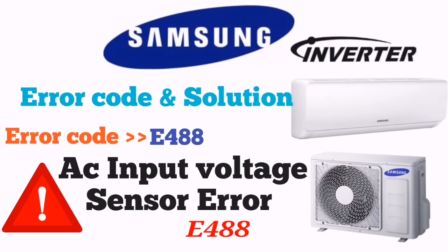When you see error E488, or LED 1 is on and LED 2 and 3 are blinking, it means AC input voltage sensor error. At that time you have to check if the connection of your reactor wire and PCB is proper or not. You have to connect it properly and restart.